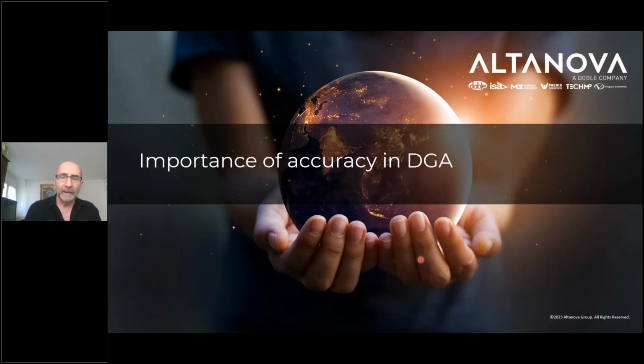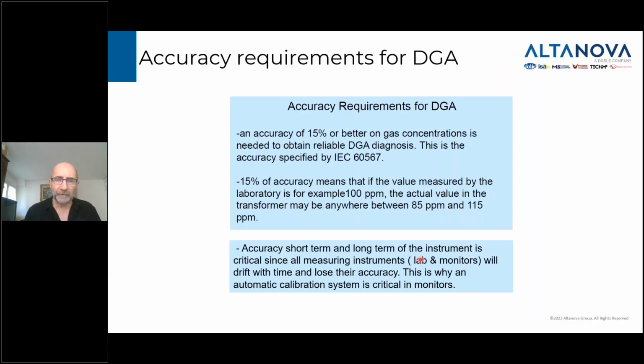Now, why is accuracy important in DGA? When you look at the IEC 60567 spec, it says that the accuracy should be less than 15%. Every instrument has an accuracy range, plus or minus 5, plus or minus 10, and that depends on a lot of different factors. But to do a very good DGA diagnostic using the DGA diagnostic tools that have been developed over the last 40 years, you have to have your system accuracy less than 15%.